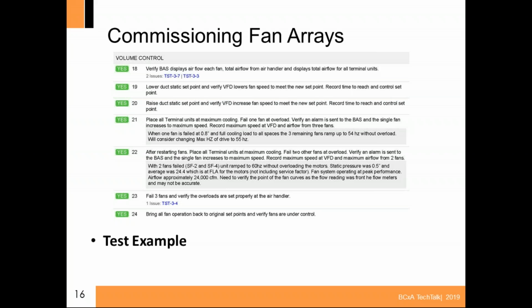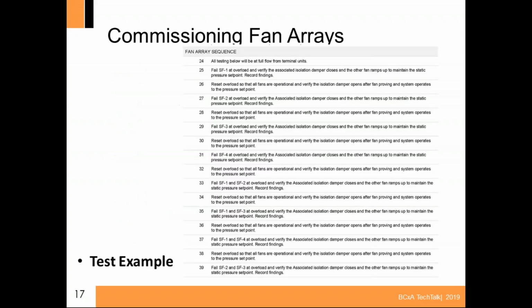On the field, line 23, it says fail 3 fans. Actually, I have an issue with that. I think when I failed the third fan, the first fan overloaded, or no, that's not what happened. Something else happened. I didn't have a way to fail it without it shutting down the unit. Then what I do is I put everything back to its original operation and let it go.